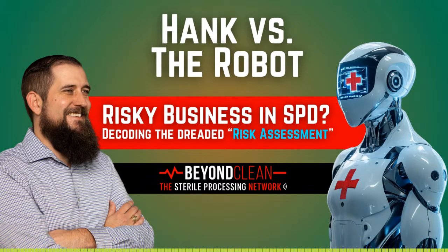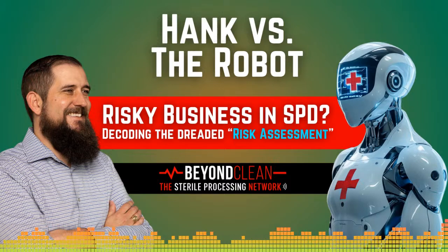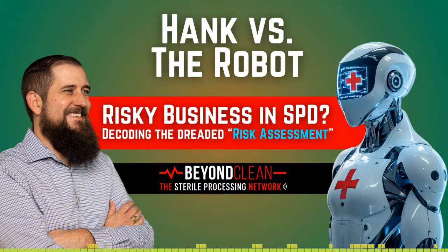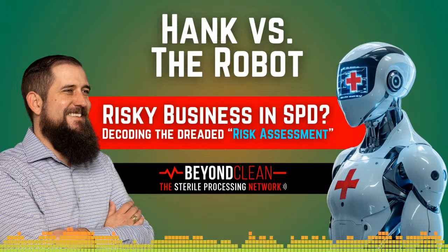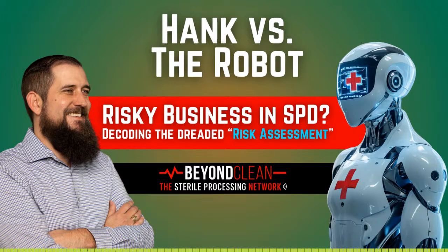2, process improvements. Checkpoints. Add extra inspection steps during manual cleaning to identify and address debris before sterilization. Documentation. Create a tracking system to log when and how cleaning failures occur. Use this data to identify trends and adjust workflows. 3, monitoring and validation. Testing. Implement routine protein and ATP tests on high-risk instruments to confirm cleanliness. Auditing. Conduct regular audits of the cleaning process and staff compliance.